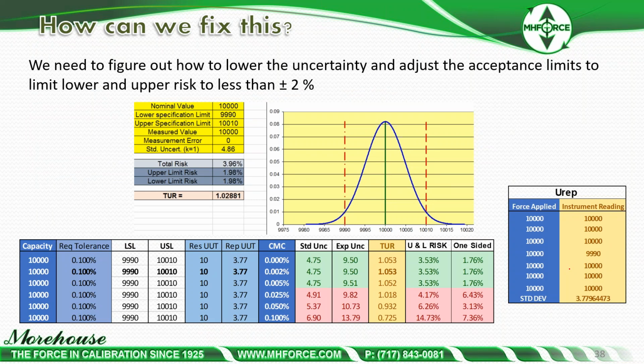You can take more readings, which takes you more time in the lab, but you can say, hey, repeatability, I can take 20 readings. Here we just started taking more and more readings, and we got the standard deviation down. So doing this, this graph here basically shows if I use dead weights with this scale and I take more readings, I can get our risk down below 2% on each side, or below 4% total one-sided risk. But as soon as I break from dead weights and I'm breaking down here to 0.025, I can no longer get this in. Again, even if I take multiple measurements, that resolution is just killer.